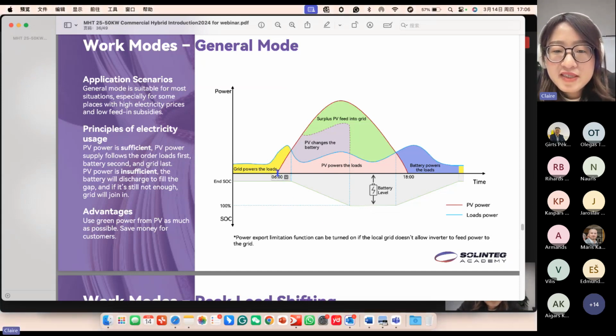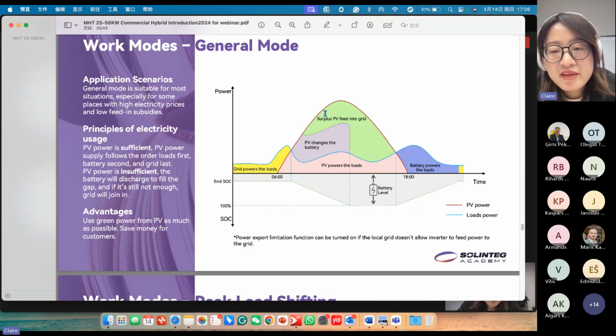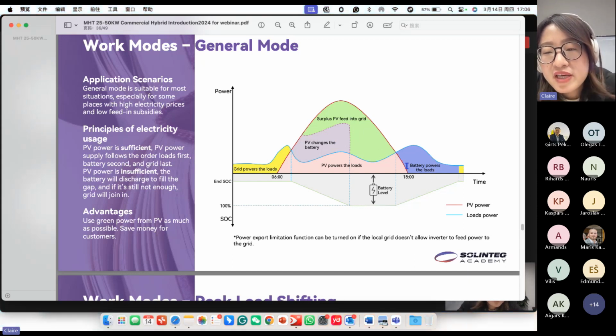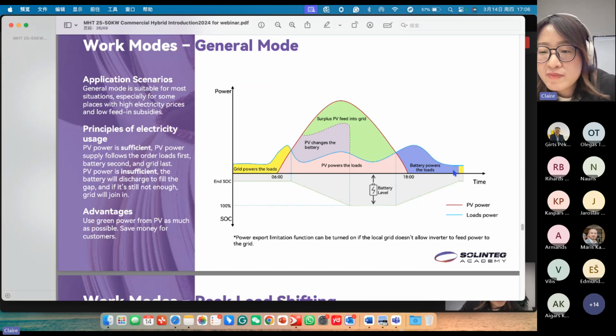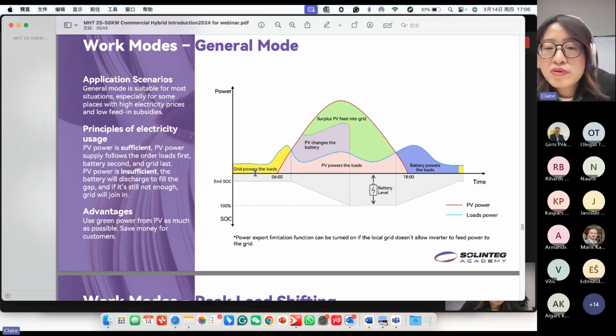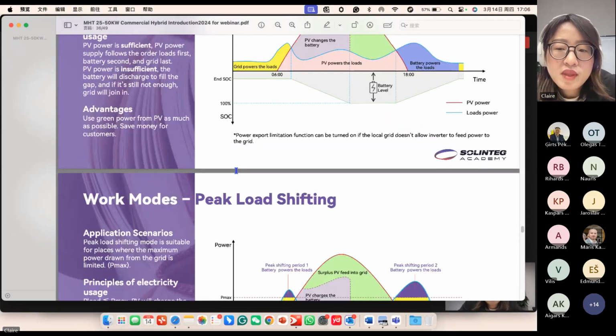In the daytime, the PV generation power can be used to supply the load, charge the battery, and the excess power is fed to the grid. And in the evening, there is no PV power generation, so the power in the battery can be used to supply the loads. If the battery is discharged to the SOC value, then in the late night, we will use the power from the grid to supply the loads.